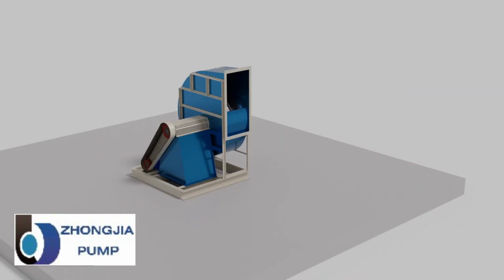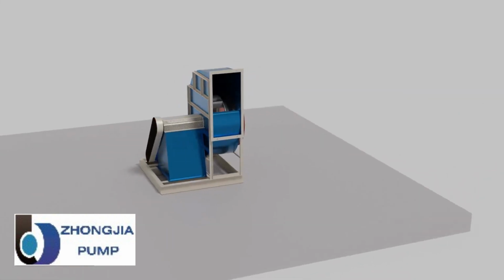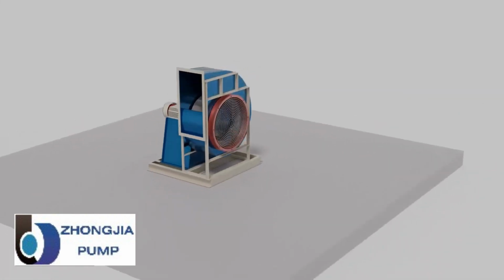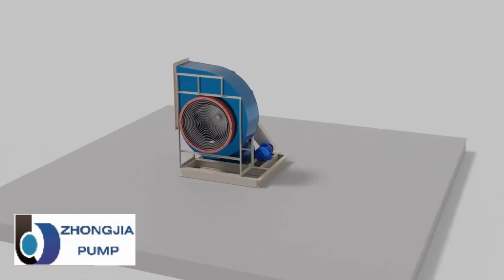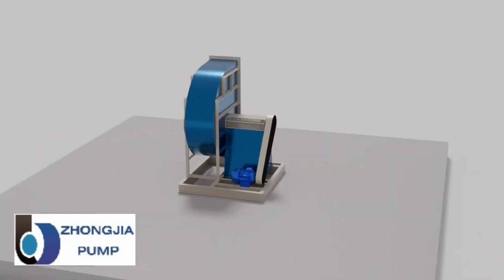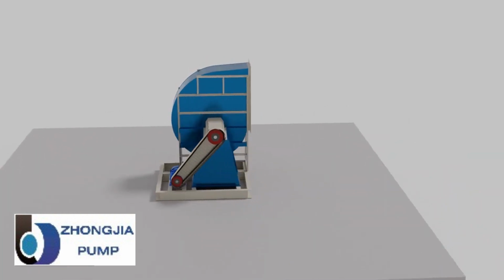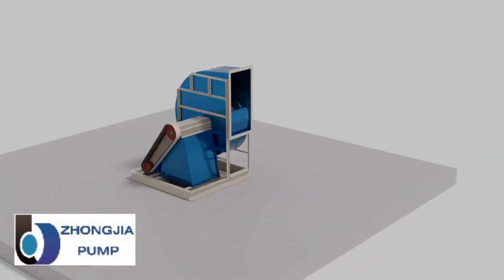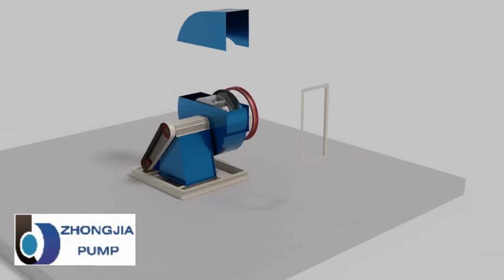A centrifugal fan is a device used to move air by imparting both kinetic and potential energy to air. Potential energy is the static pressure and kinetic energy is the velocity pressure. It works on the centrifugal effect principle. First we will see the basic components of a centrifugal fan.